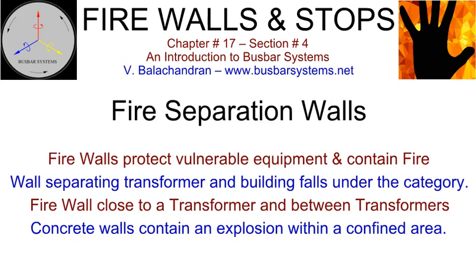It is a practice to install a fire partition wall close to a generator transformer and building, and between the single-phase generator transformers of a delta-connected system. These are concrete walls that are expected to contain an explosion within a confined area.